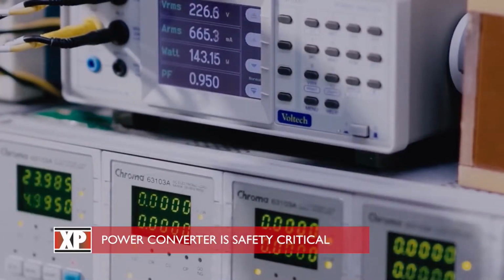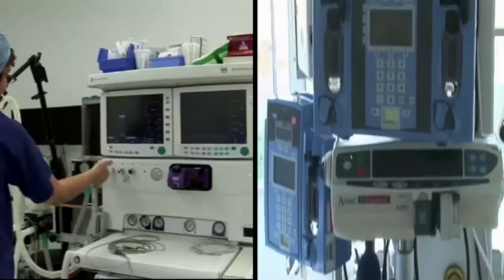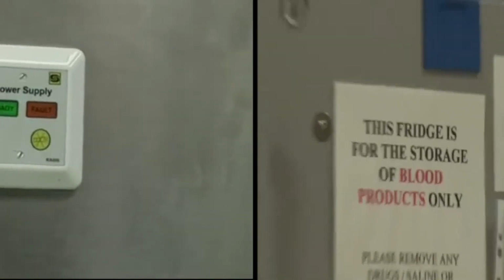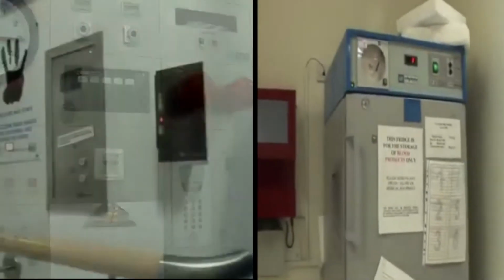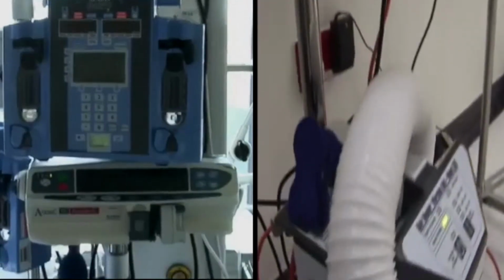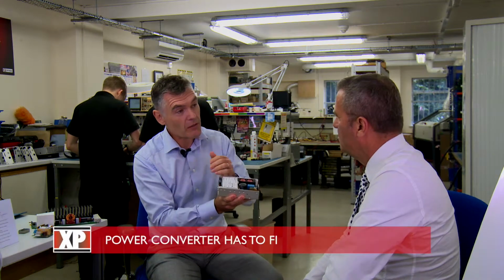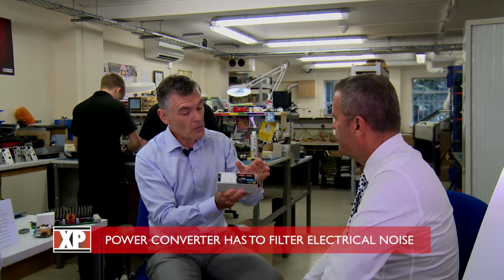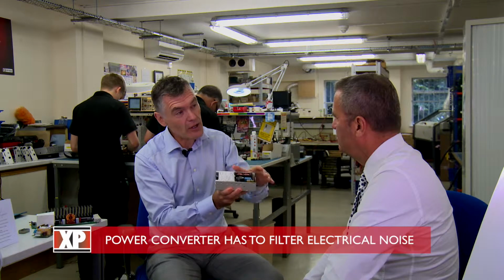The power converter also performs another important function: it stops electrical noise from the mains getting into the customer's equipment and interfering with it — which could be very sensitive, for instance ultrasound or a communications device. There's also legislation to prevent the customer's equipment, if it produces electrical noise, from putting that noise back through the mains to interfere with other equipment. So the power supply has to act as a filter in both directions.